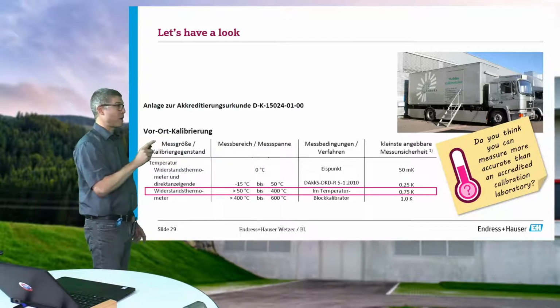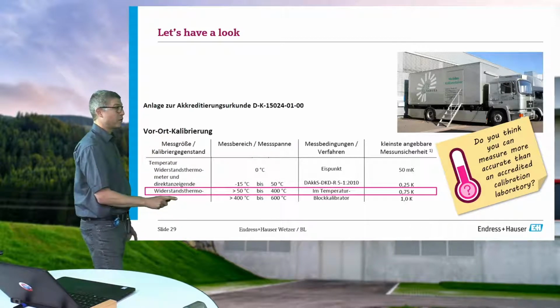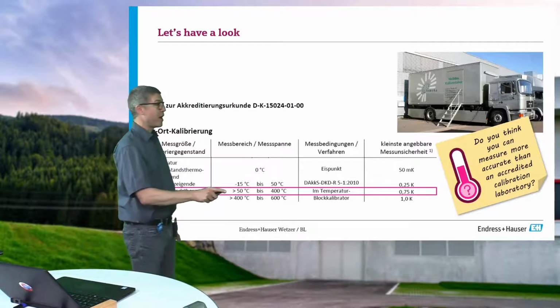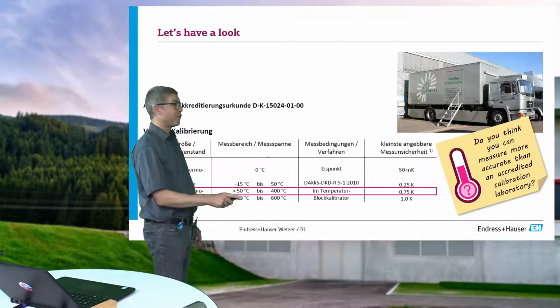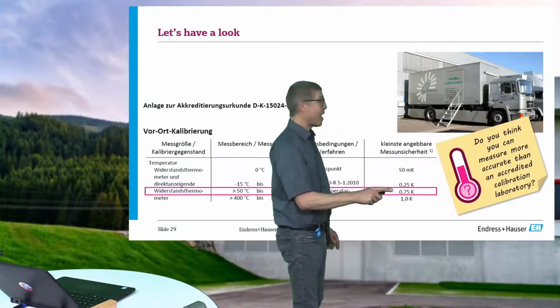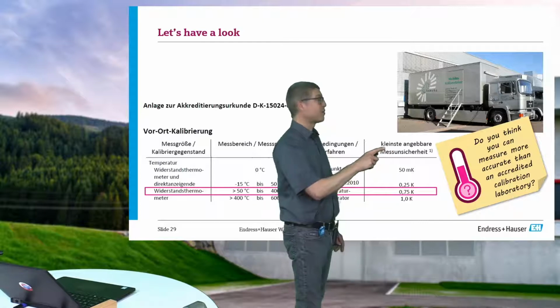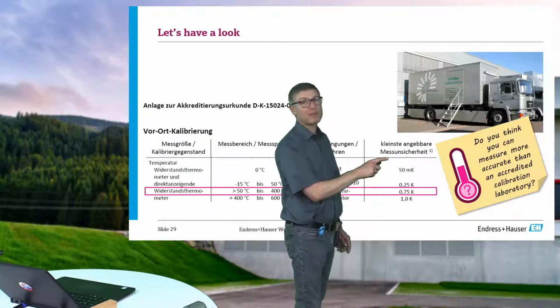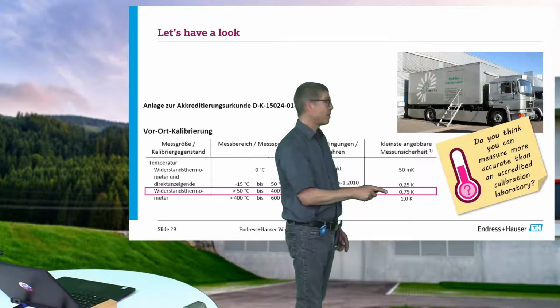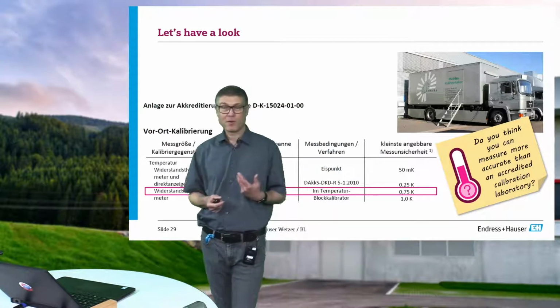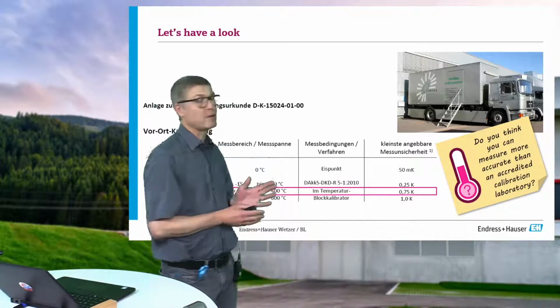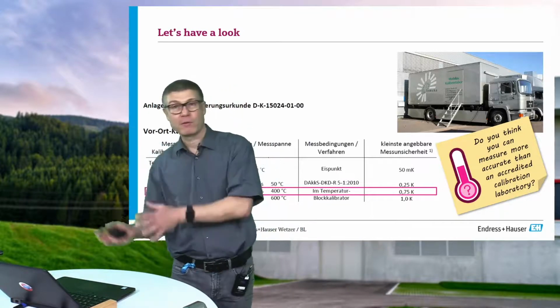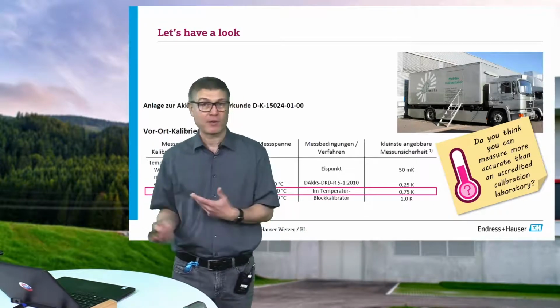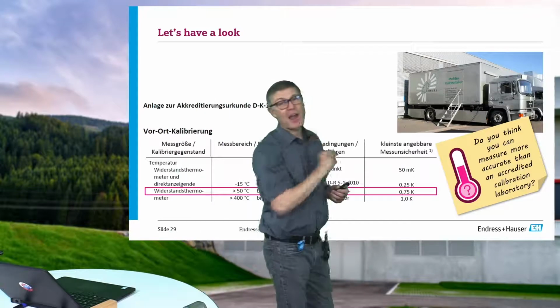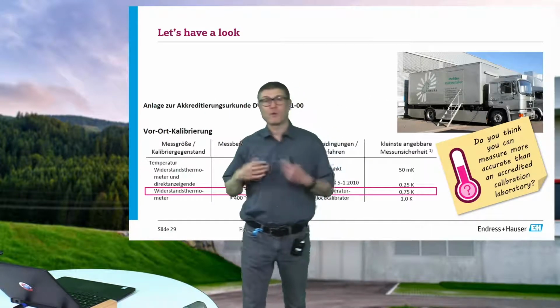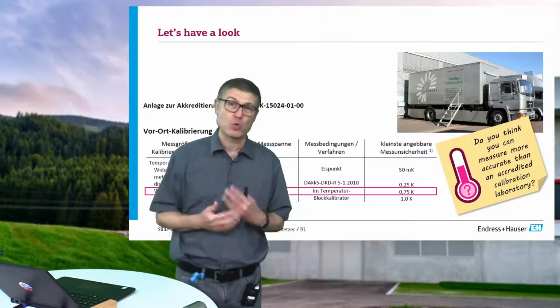on-site calibration, you can imagine, and this means resistance, and you see thermometer. So for the range we are talking about, between 50 and 400 degrees, they are able to do a calibration with the smallest possible measuring uncertainty, that's the German word here, of 0.75 Kelvin. So that means if you're using a dry block calibrator for the temperature range which is relevant for food and beverage and life science industry, a specialized company can do an uncertainty of 0.75. Can you imagine that you do it better?